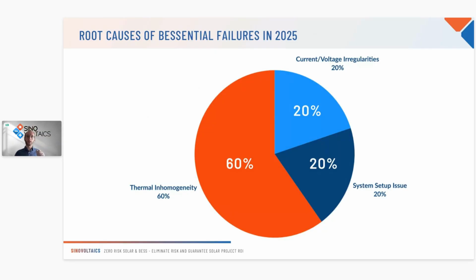What's really interesting is that the traditional FAT focuses only on checking the capacity of the container as well as the round trip efficiency, RTE. They overlook, they don't even look at, the thermal implications of the performance test. That's why running BESSential is, I believe, absolutely critical if you want to ensure your BESS assets will perform as expected for 10 or 15 years.